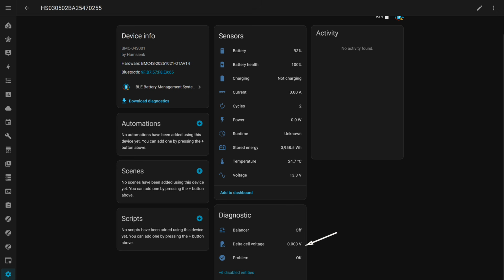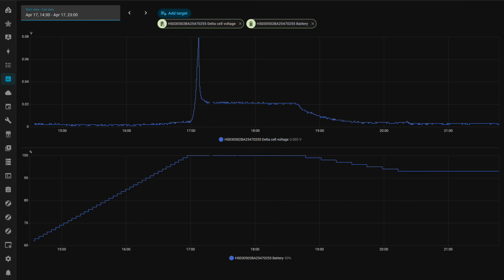For better clarity, let us look at this as a graph. At the top is the voltage difference between the cells; the larger it is, the worse. At the bottom is the battery charge level. We can see that the delta peak coincided with reaching 100% charge, then dropped sharply, but the difference still remained above normal, more than 20 millivolts. During discharge, however, the situation began to improve sharply and very quickly returned to normal.